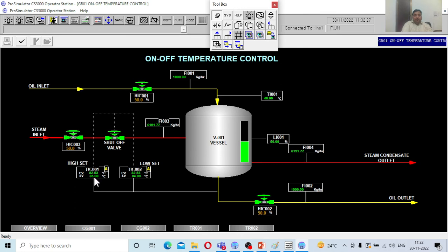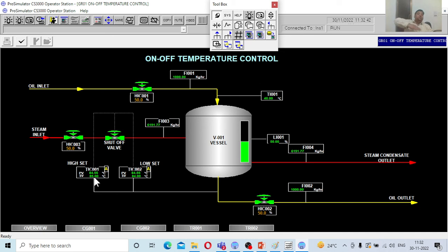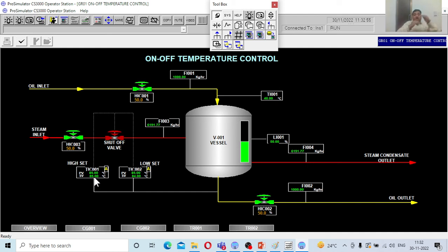Now the process value hits 85 and the valve turns off; the moment it drops to 84, the valve opens again. This high frequency of on and off causes wear and tear on the control valve — 100% open, 100% close, 100% open, 100% close — which is not suitable. That is why for on-off control systems, the boundary between high set and low set should be sufficiently wide to reduce wear and tear on the connected control valve.